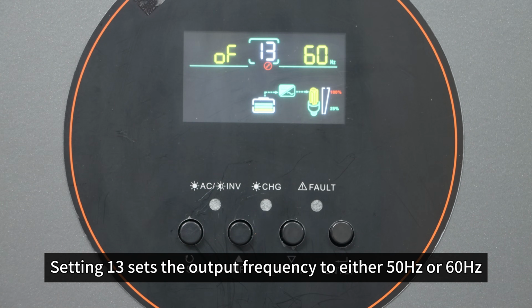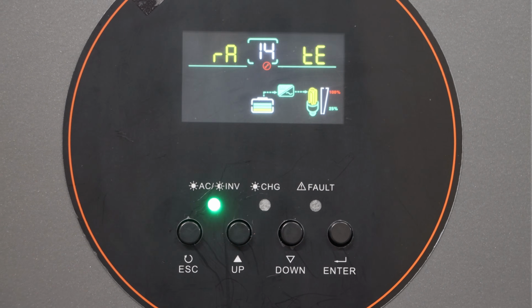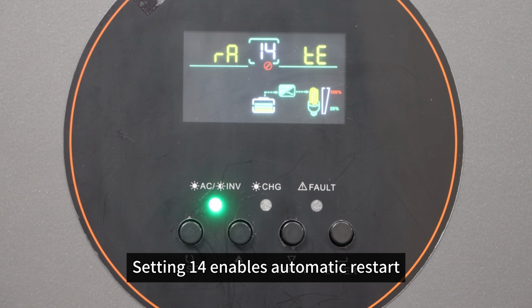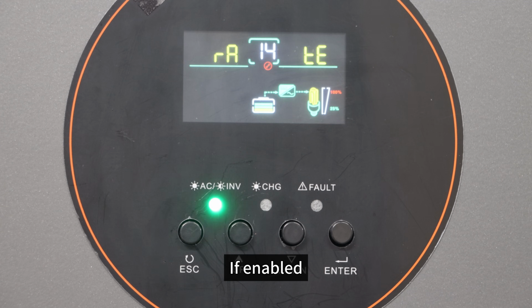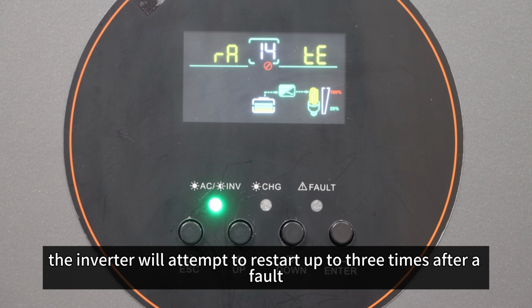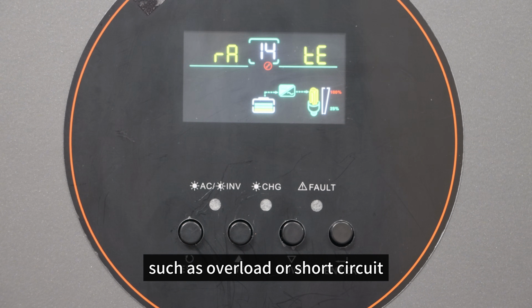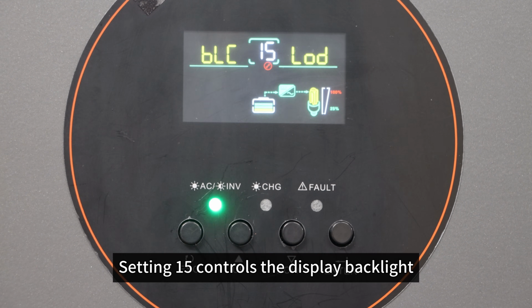Setting 13 sets the output frequency to either 50 Hz or 60 Hz. Setting 14 enables automatic restart. If enabled, the inverter will attempt to restart up to 3 times after a fault, such as overload or short circuit. Setting 15 controls the display backlight.